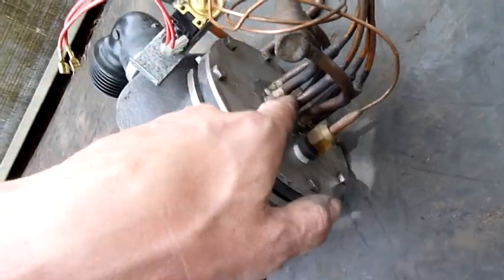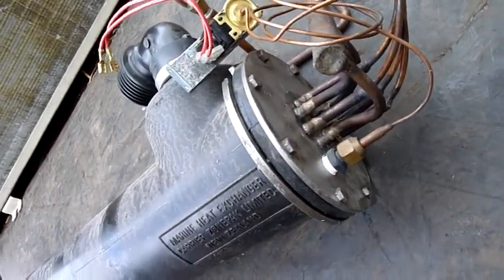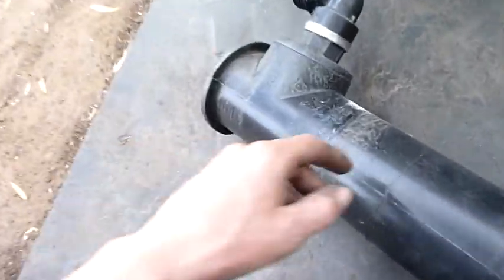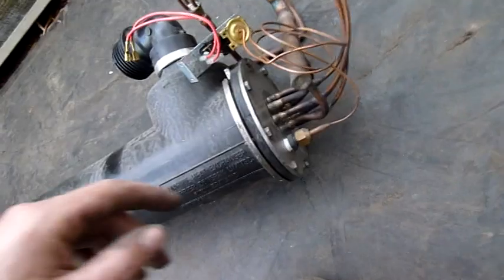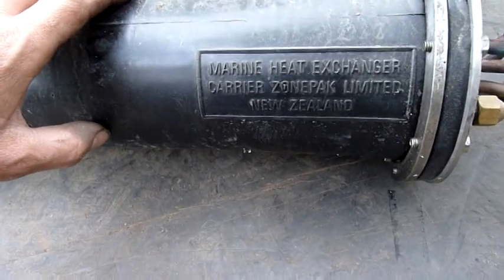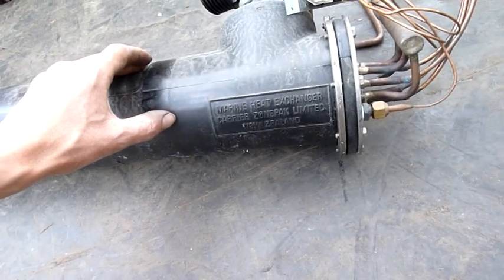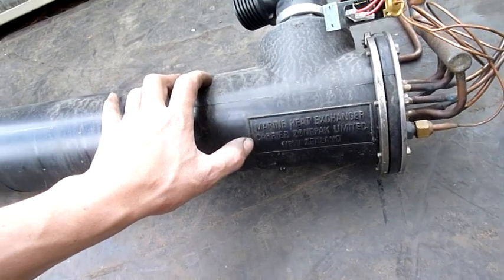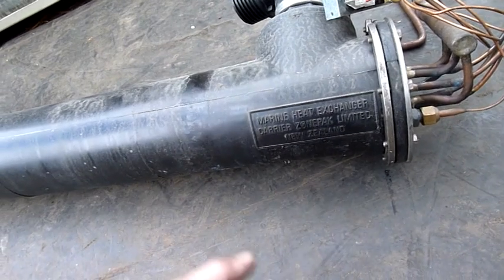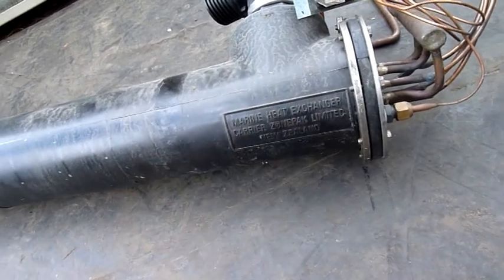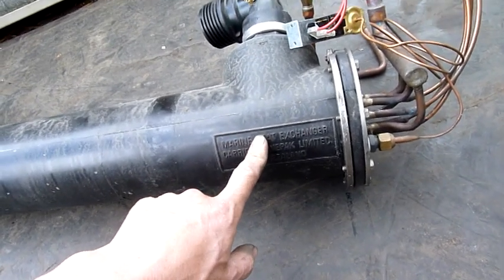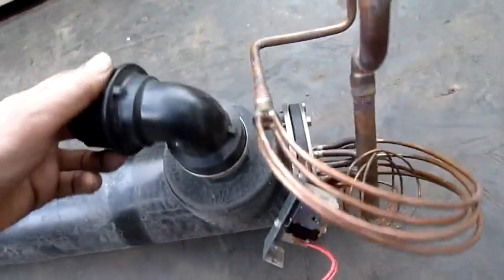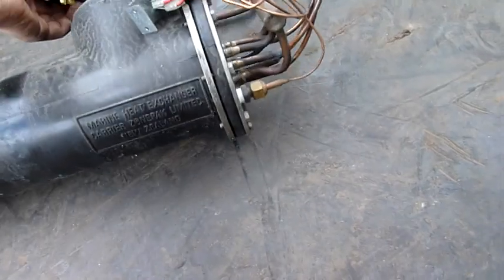But yeah, you can see the refrigerant tubes going in and out of the internal exchanger. I'll try and get this open. I'll probably unscrew one of these plugs and just give you a quick look inside. I don't want to disturb the end gasket because I know that's sealed. But yeah, it's a marine heat exchanger. I was talking to a friend at work and he suggested marine air conditioning will use this, or big refrigeration from the UK suggested the same sort of thing for an onboard fridge or something like that. When you've got a big abundance of water, instead of having an air-cooled fan coil assembly, you just install these things and circulate water through them. It's a lot easier. You don't have fans and other stuff running, it's just a pump. So that's that.